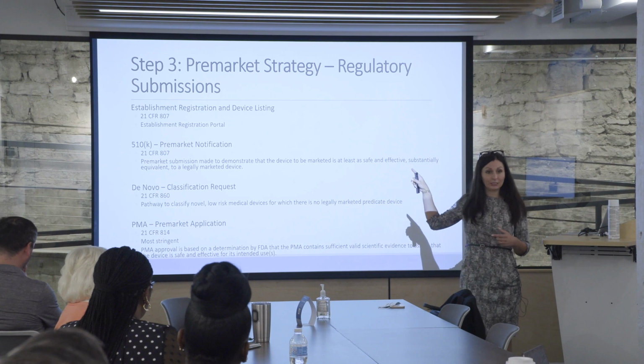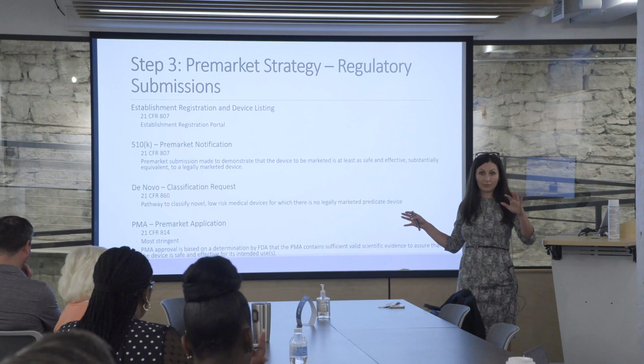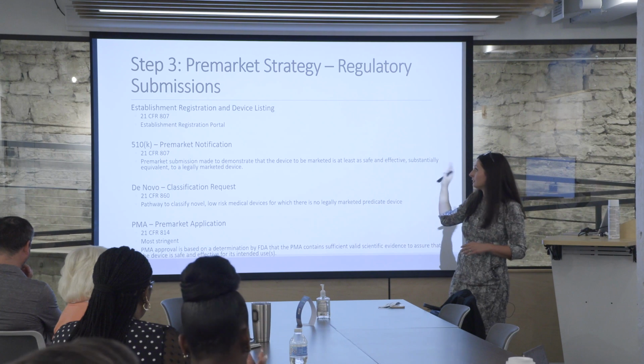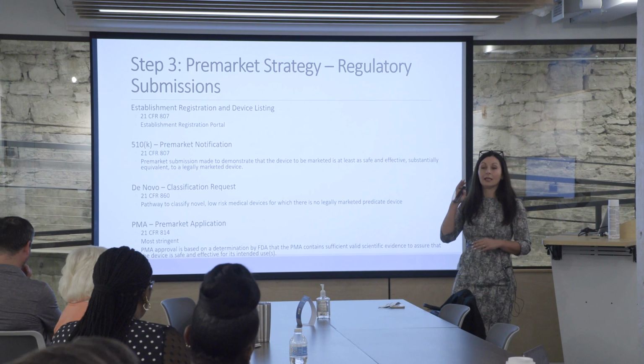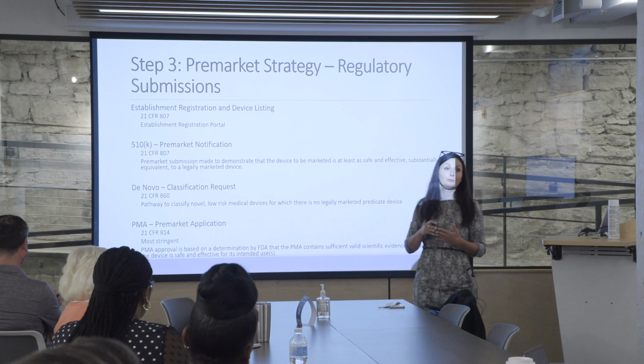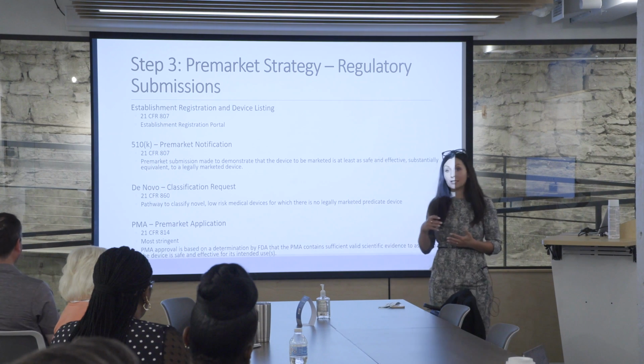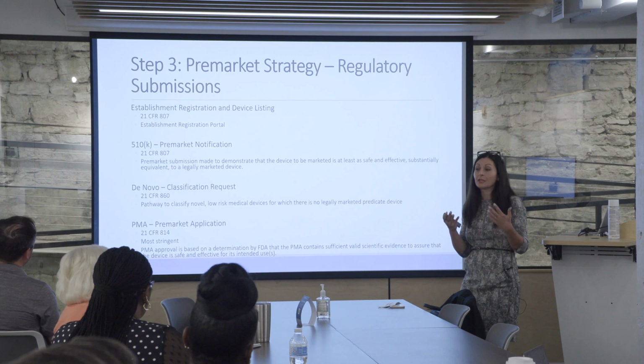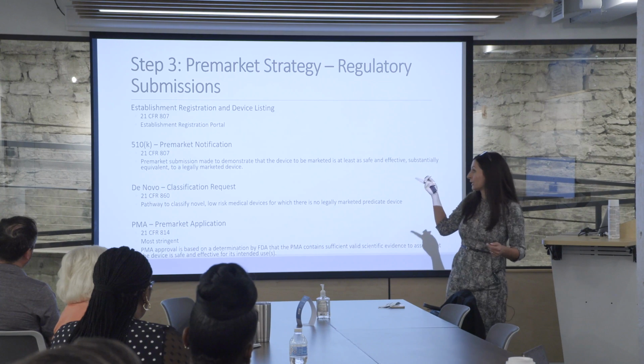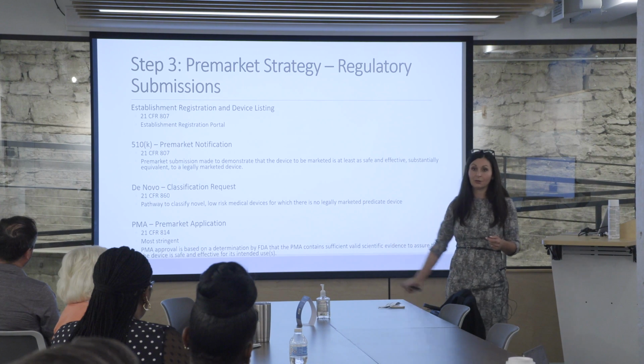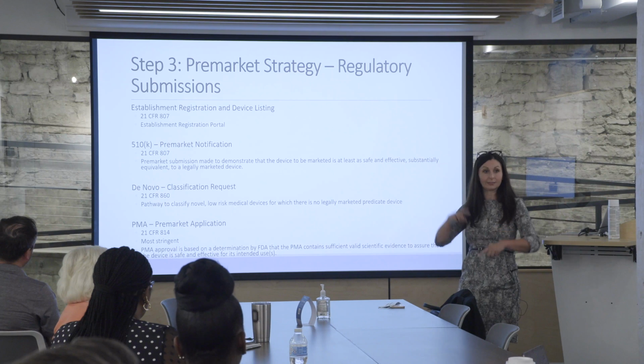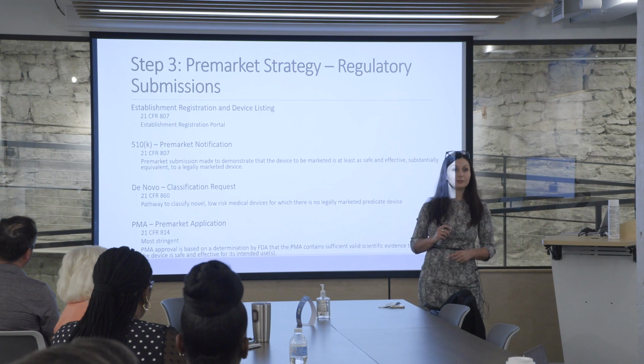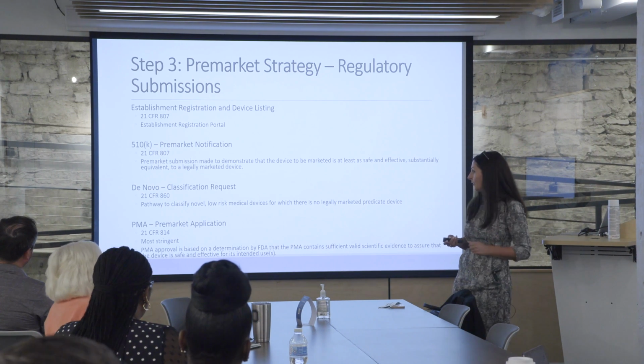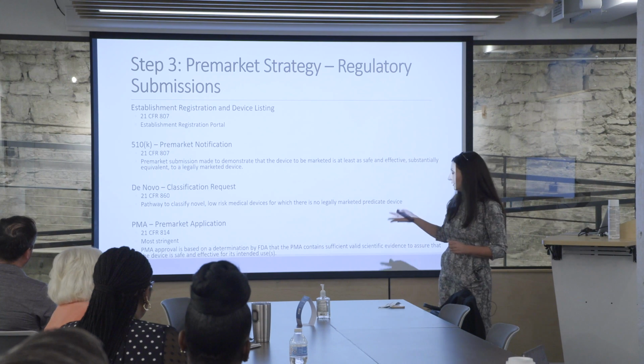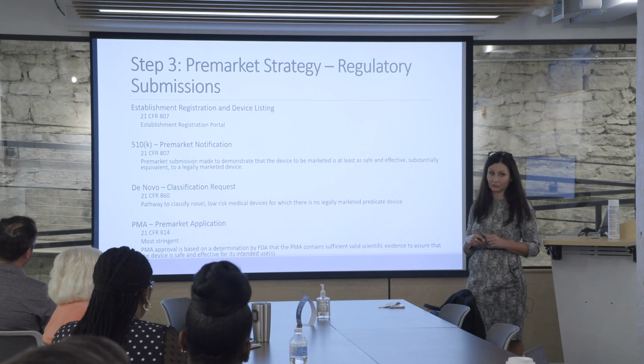Everyone has to do registration and listing. So that's regardless of what kind of medical device you have, everybody has to do it. It's the same fee for everyone. And you have to register and list your device before you put it into commercialization. So that basically means if you have a Class 1 product, you can do that right before you're ready to commercialize your device. If you have a Class 2 product where you have a 510(k) or a De Novo, you actually have to wait until you get that cleared to do your device listing. So you can't do it before then. Same with the PMA. You have to wait to do your establishment registration and your device listing.